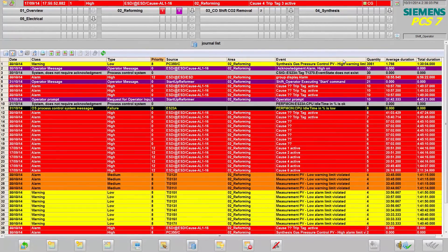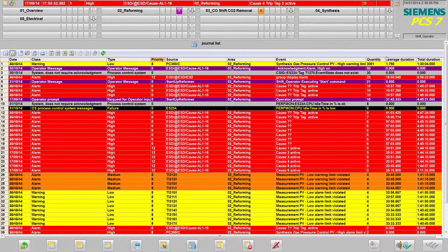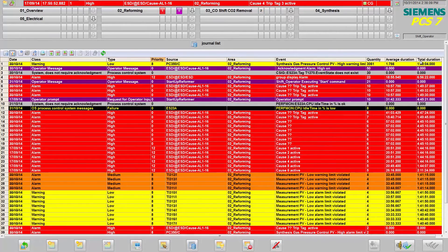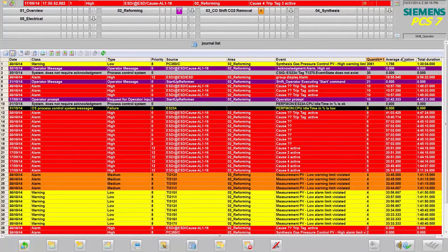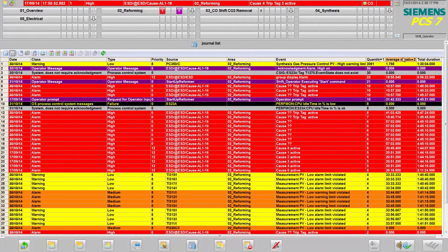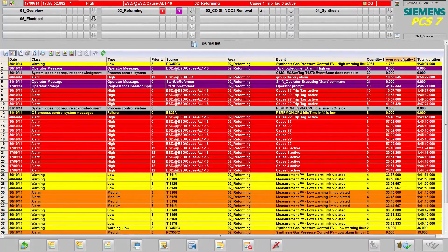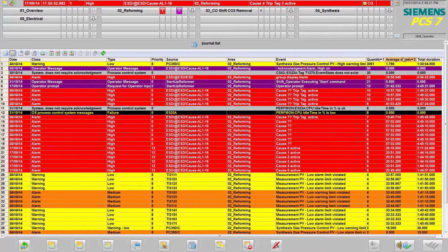This includes, for example, the number, average duration, and total duration. If I want to know at which measuring points short-term alarms occur most often, I have to set the first filter to the number and the second to the average duration.